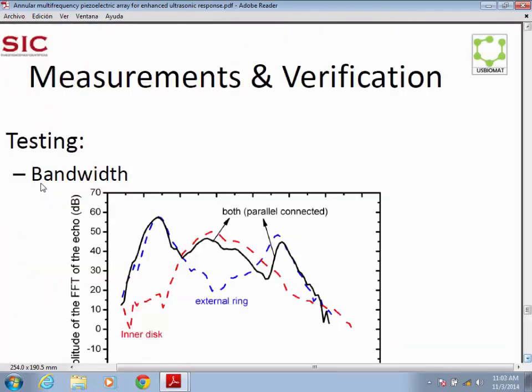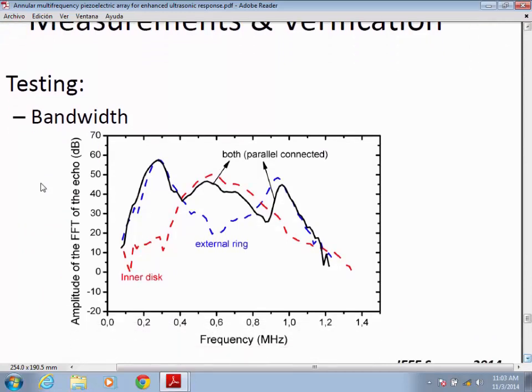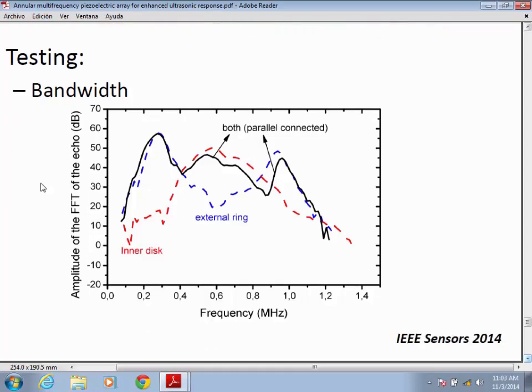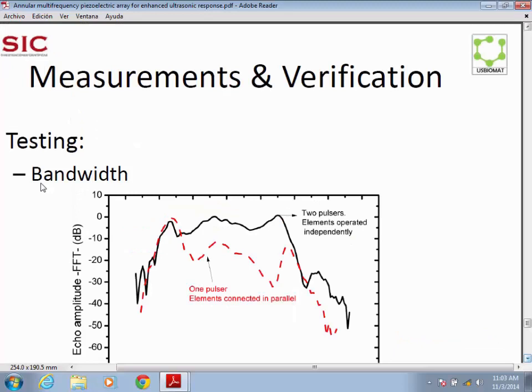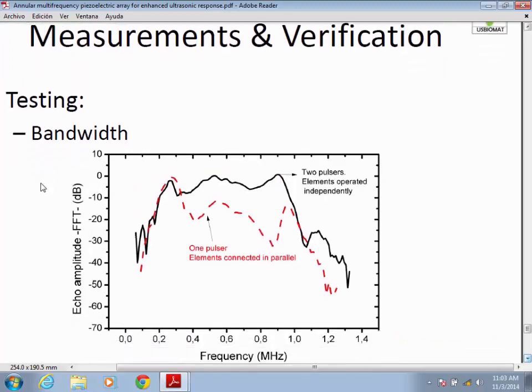So once we start adding these bandwidths together in order to see what it looks like, this is the inner disk, the red one, in the center there. We have the outer ring with the initial resonance, and then the second order, and the black one is the sum of all the bandwidth on the overlapping bands of the two elements. In this case, we're using one pulser for the red one. It means we are using the same setting to excite both elements of the array, so we get a not so flat response from the system. But when we equalize this exciting signal, we can get a much flatter response, much nearer to what we wanted to get.